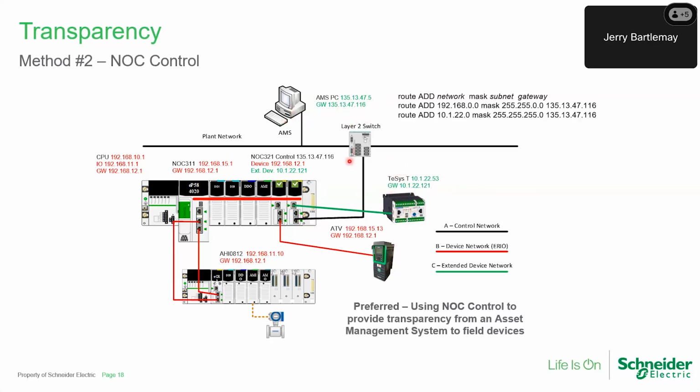Well, first of all, for that message, it needs the gateway to be this NOC module. Well, in order for that to happen, if you've got 15 M580s out here, you're going to have 15 gateways depending on what message you're trying to send to devices on those 15 controllers. And so we use a route statement.